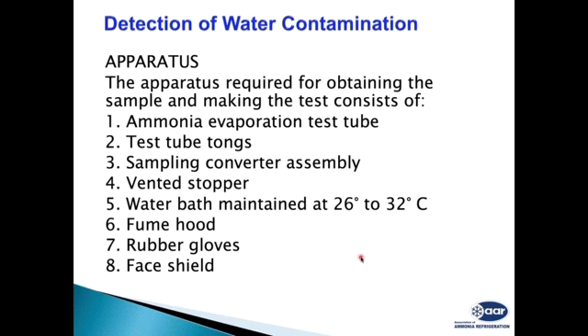Can we detect if there is water in our system? Like air, we can find the pressure difference between the actual pressure and the saturated pressure corresponding to the liquid temperature. That's the easy way. For ammonia and water it's a bit more difficult, but it can be measured. You need an ammonia evaporation test tube, test tube tongs, the sampling converter assembly, a vented stopper, and a water bath in which you put the beaker, plus a fume hood, rubber gloves, face shields. Safety equipment is very important.